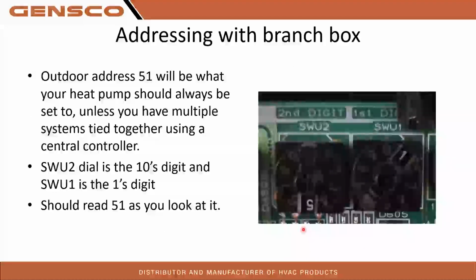So how do we address the system? So this is looking at your heat pump. On the top right of your boards, you will see 2 rotary dials like this. Guys get very confused on the first digit, second digit thing here. Basically, if you address it at 51 to where it reads 51 as you look at it, 5 on the left, 1 on the right, you're good to go. So again, 51 on your heat pump, this will probably be 99% of your installs out there.